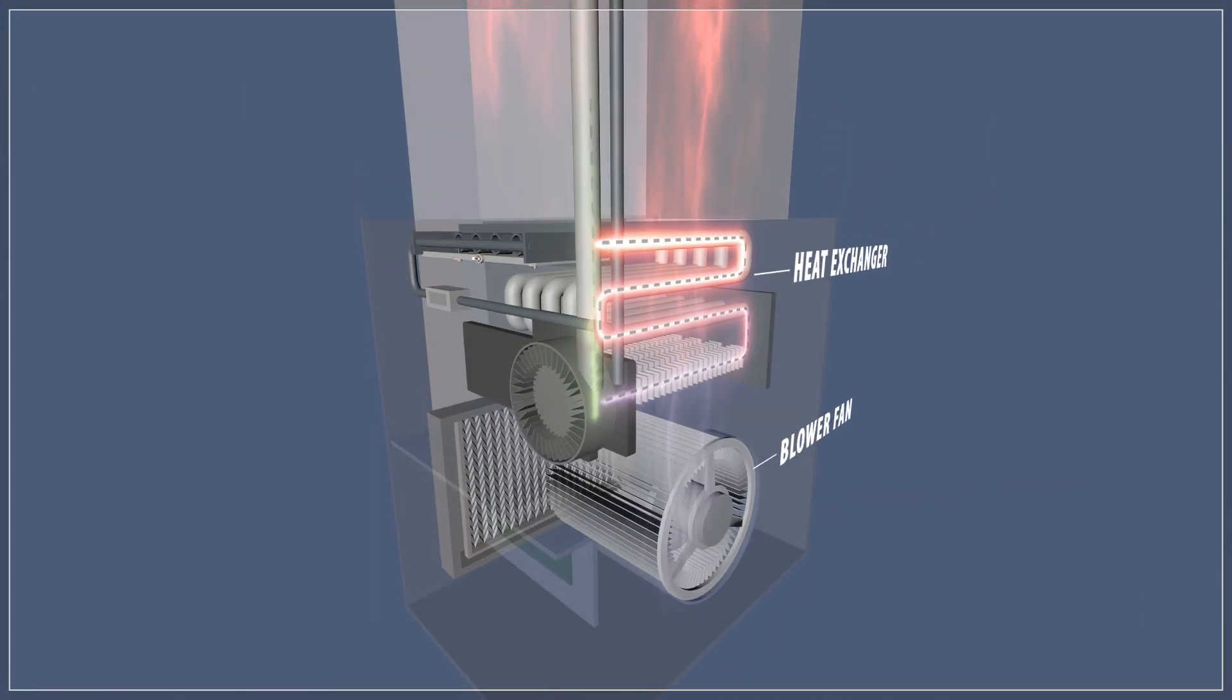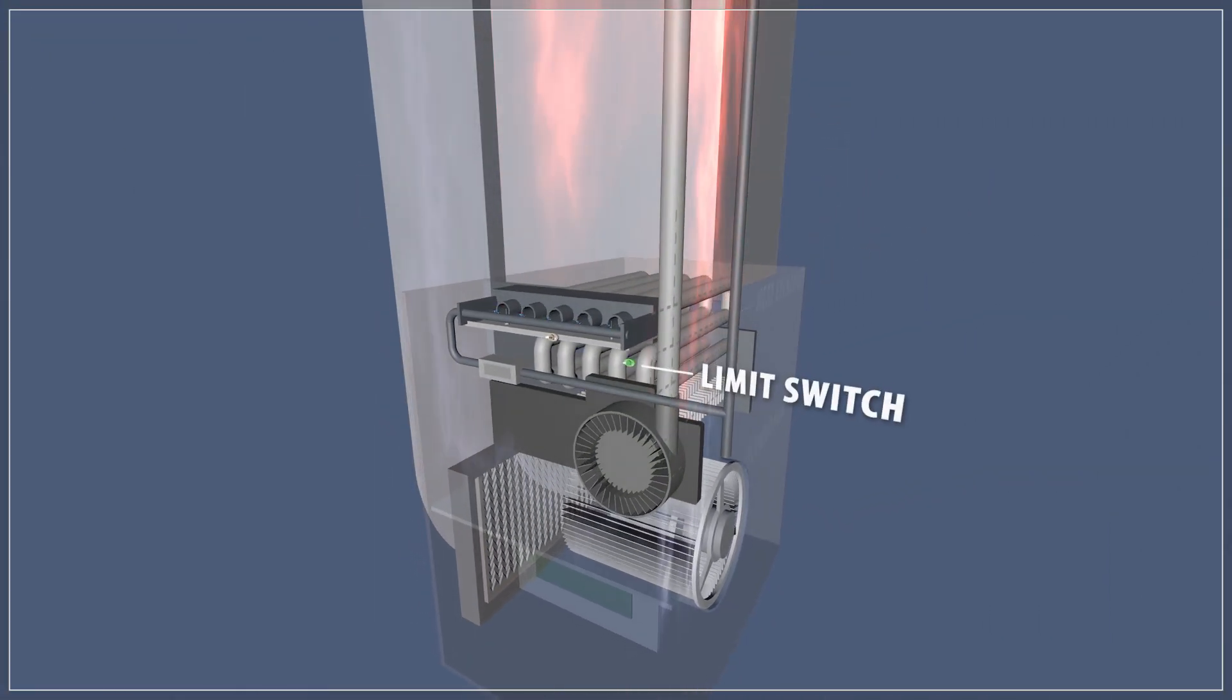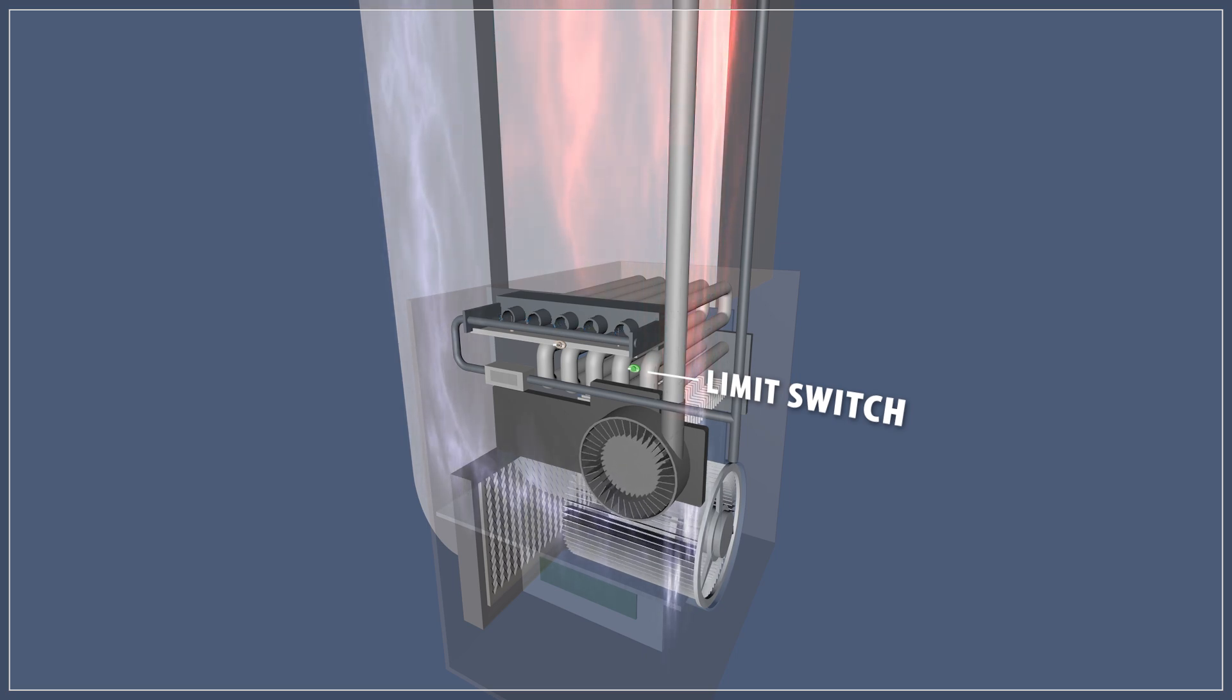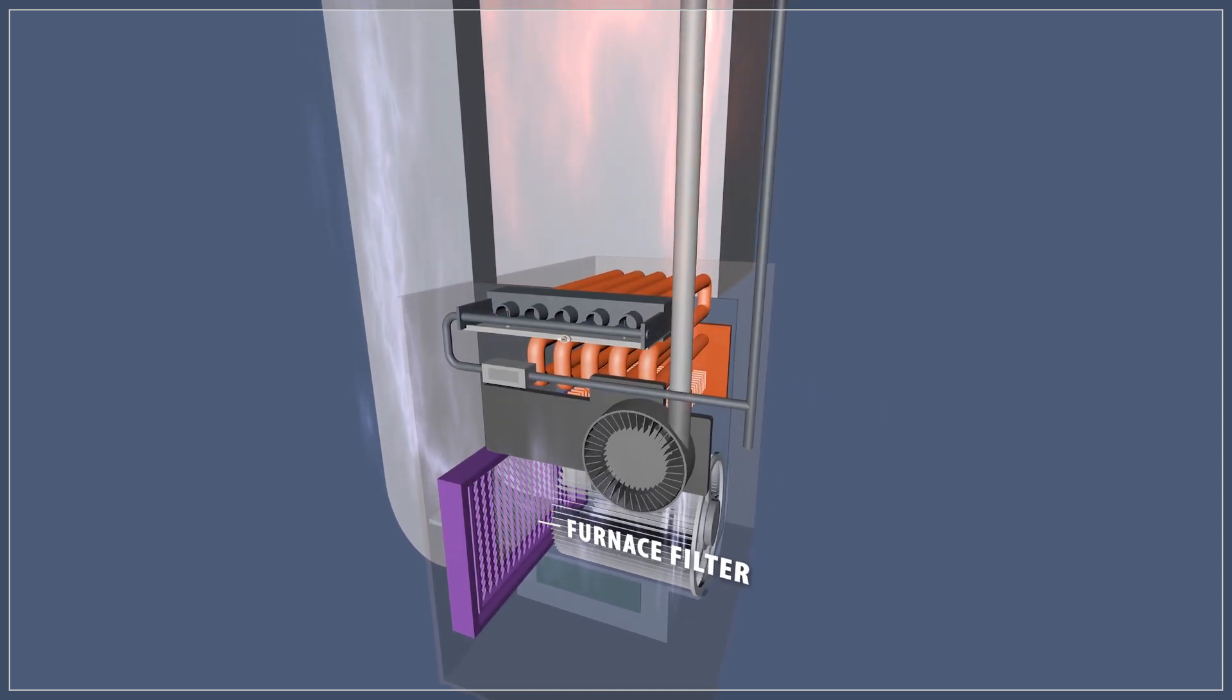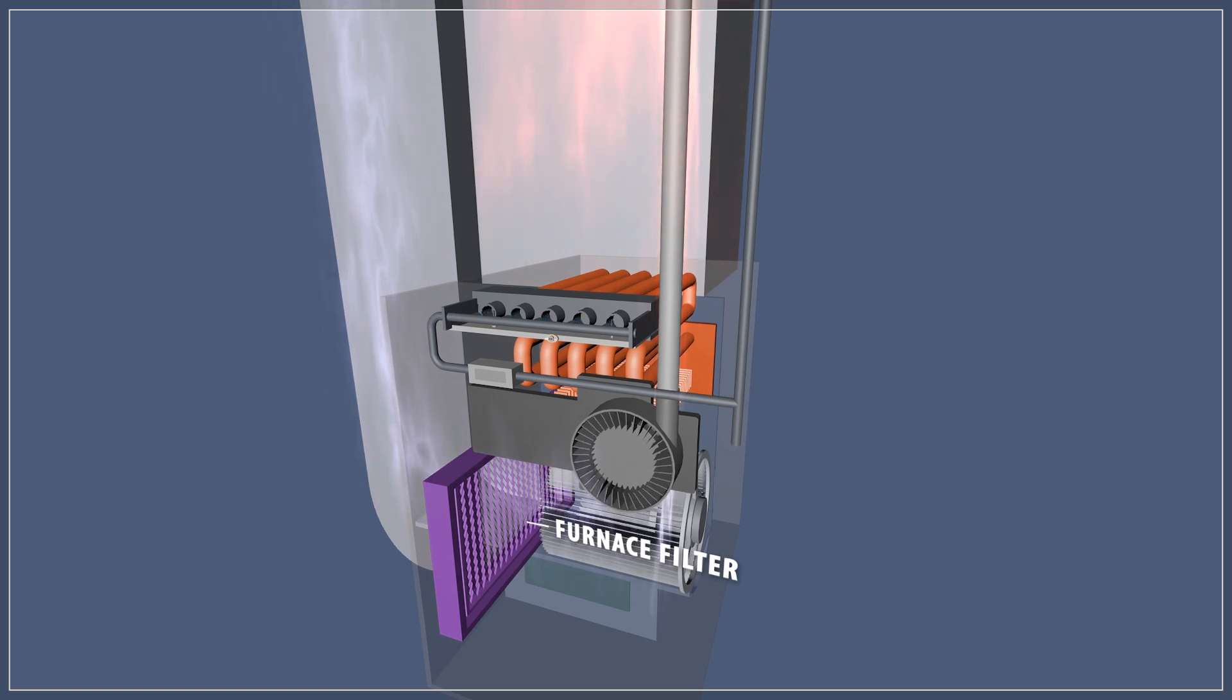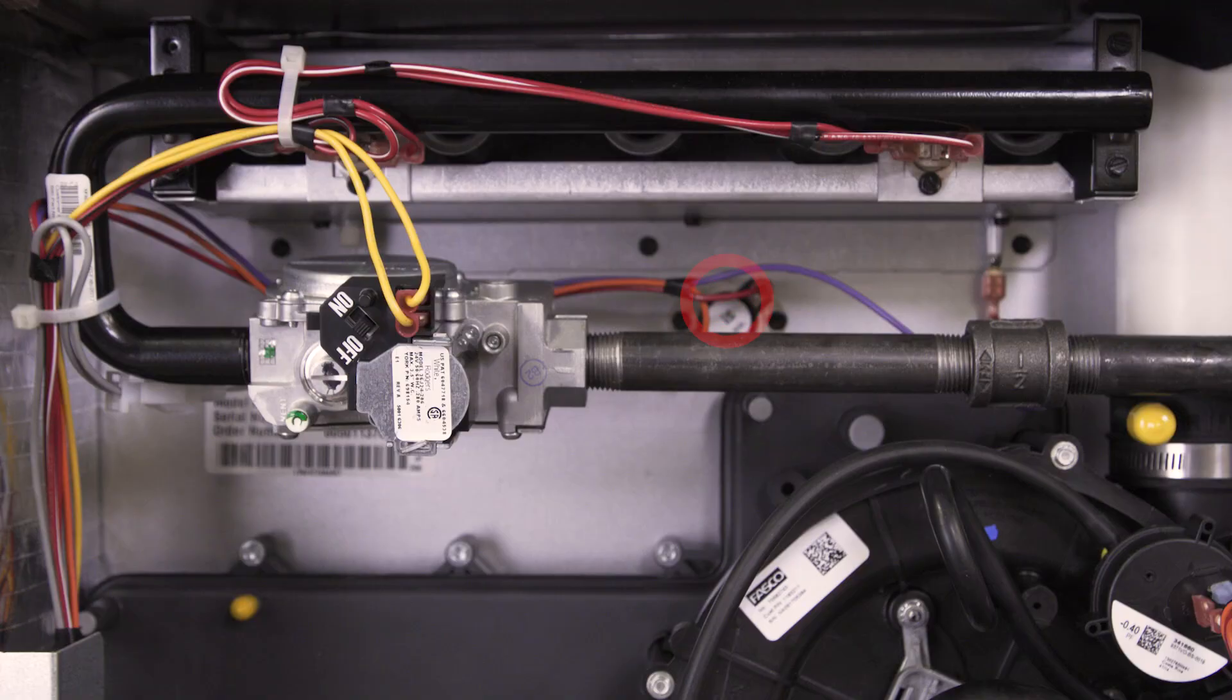The limit switch monitors the temperature of the air passing over the heat exchanger and will shut off the furnace if the system overheats. Any restriction of the airflow might cause the heat exchanger to overheat. This is why it's essential to replace the furnace filter every three to six months. If the airflow is good and the blower fan cycles on and off, then the limit switch could be defective.